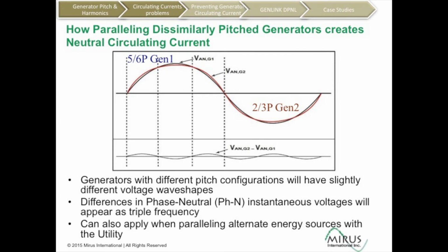So why do we have circulating neutral currents when we have generators of dissimilar pitch being paralleled? This graph shows the waveforms from two generators of different pitches. One could be a 5/6 pitch generator, shown here in blue, and this generator has a higher peak voltage and slightly lower shoulders, and then the other, being a 2/3 pitch generator, has a lower peak voltage and broader shoulders.